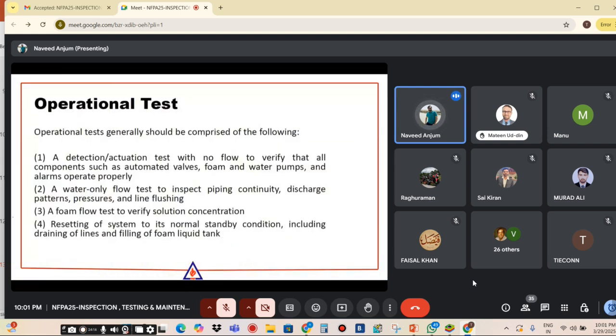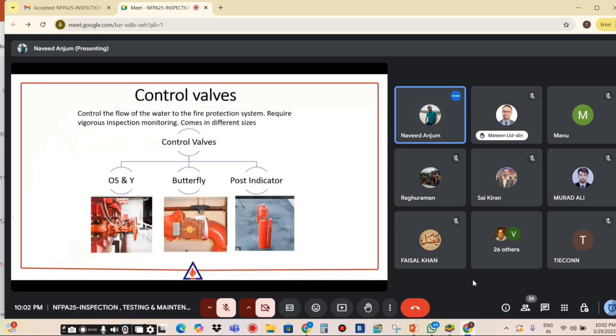Like in operation testing, a detection actuation test with no flow to verify that all components such as automated valves, foam, water pump, and all alarms operate properly. Then a water only flow test to inspect piping continuity, discharge pattern, pressure, and line flushing. A foam flow test to verify solution concentration, and resetting of the system to its normal standby condition. This is basically operation testing of your foam system.